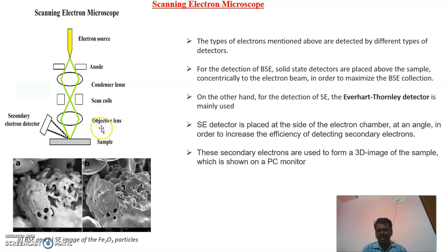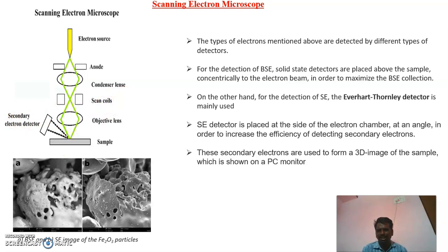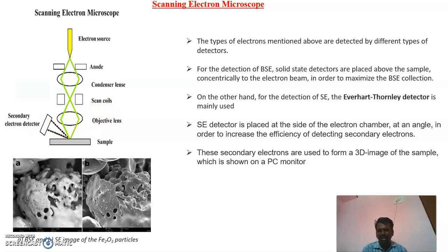The detectors for the backscattered electrons are kept above the sample, and detectors for the secondary electrons are kept at the sideways of the path of the electron beam. These respective detectors collect the respective electrons, and these electrons give a perfect image of the surface of the material on a computer monitor. This is the working principle.